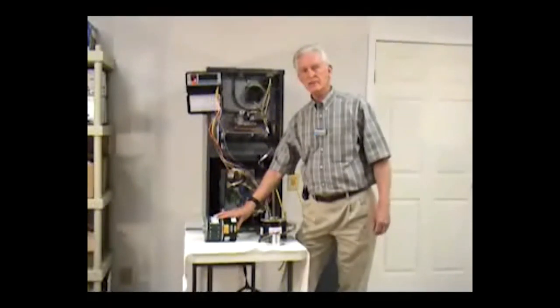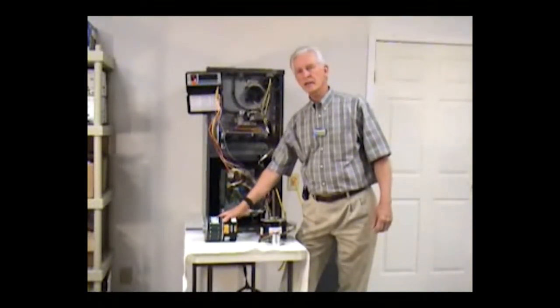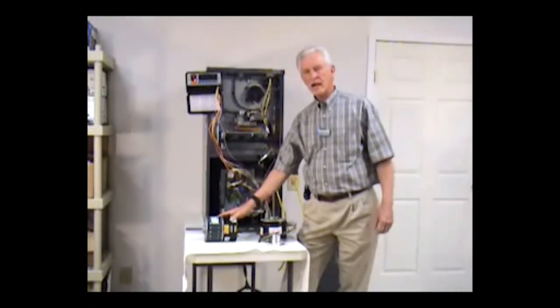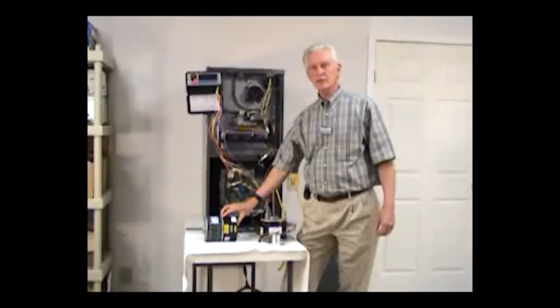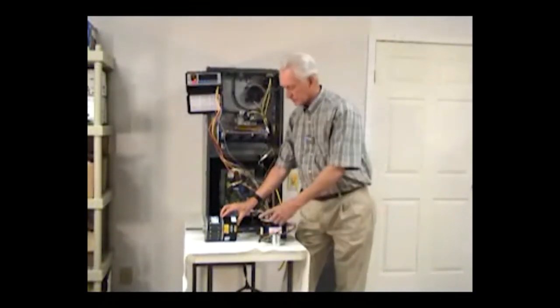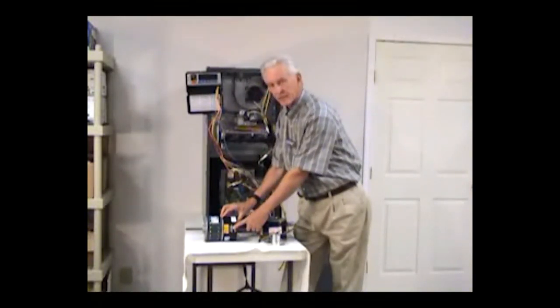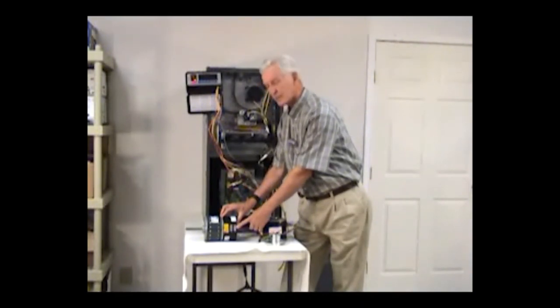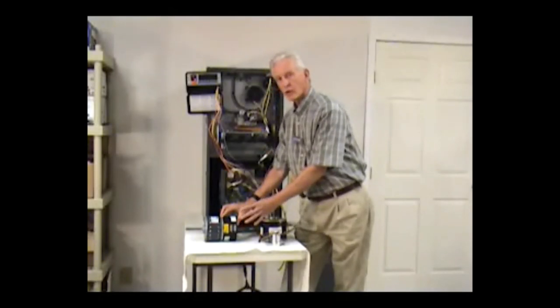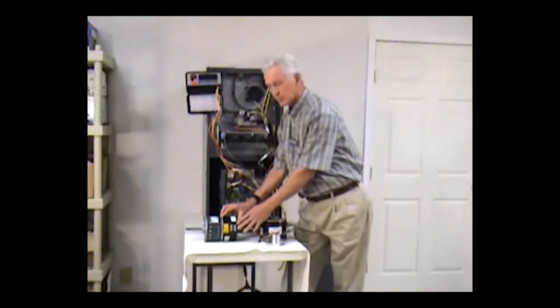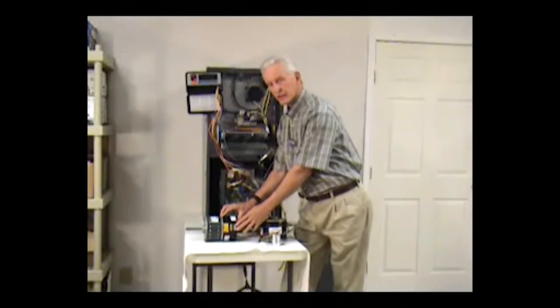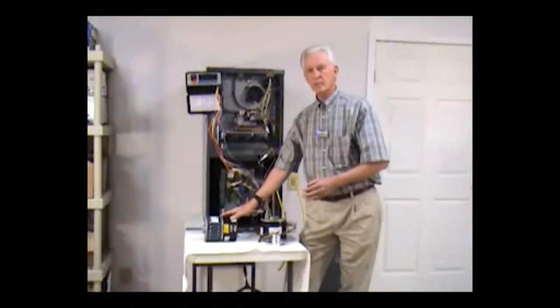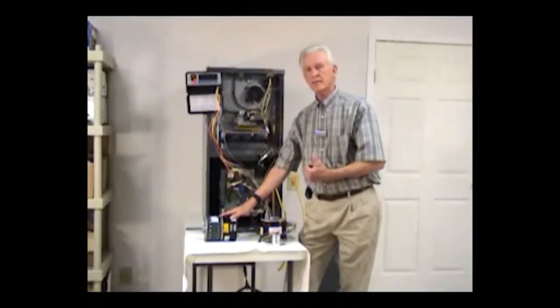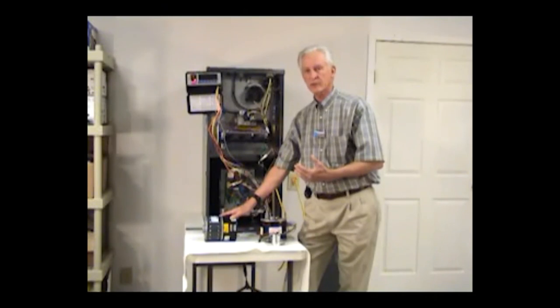The next one that we have here is a module that was used predominantly by the Carrier Corporation on their high-end units. And that module looked identical to this one with a couple of variations. One that stayed the same is, here we have line voltage hooked up to this motor. That one was the same. And then we have a 16-pin connector, and that is the same as far as the connector, but we're only using four wires in the 16-pin connector to communicate from a special thermostat to the motor itself. And those, again, were used specifically in the high-end equipment by Carrier, and you're probably not going to find that in any of the other, or many of the other manufacturers' pieces of equipment.